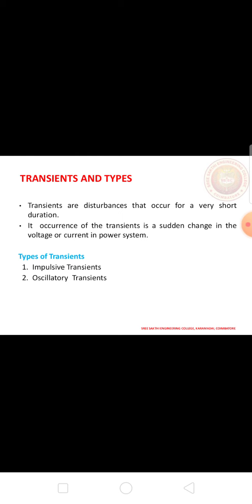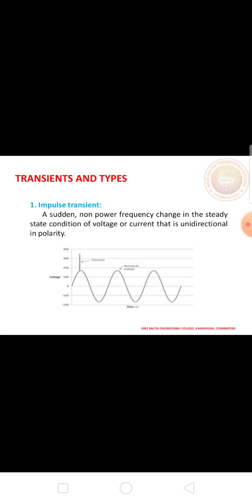Next, first, impulsive transient. It is a non-power frequency event in which the steady state condition of the voltage, current, or both change suddenly. The most common source of impulsive transients is lightning strikes. It can occur because of a direct strike on a power line or from magnetic induction or capacitive coupling for strikes on an adjacent line. This is called impulsive transients, and the main important types of impulsive transients are based on the rise time and duration. Impulsive transients are further classified as nanosecond, microsecond and millisecond impulsive transients.